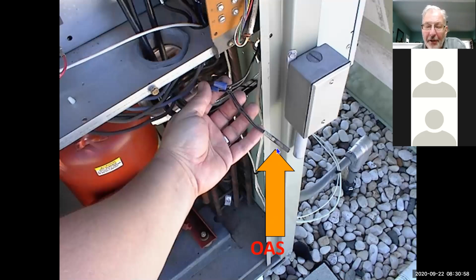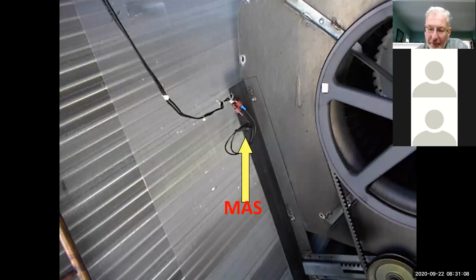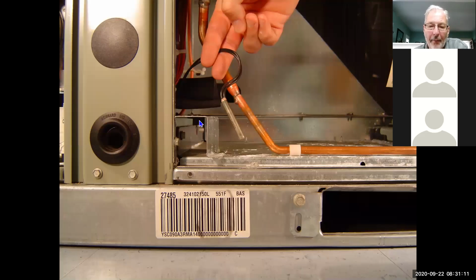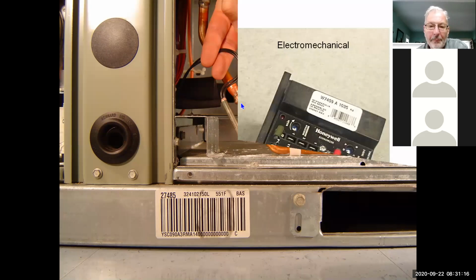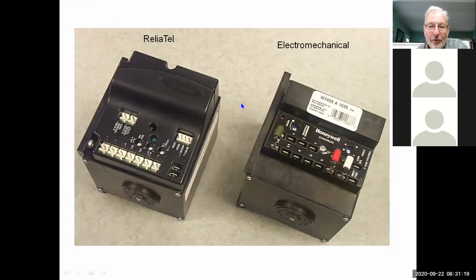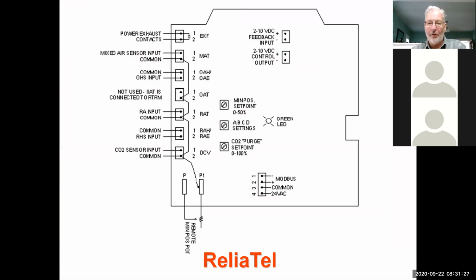The mixed air sensor on the older units is up inside this corner panel here. You have to reach back in there, grab that, and slip it out of its grommet. On the new units, the Reliatel, the mixed air sensor is down here by the foot of the compressor. And the old units, we don't use Honeywell anymore, but there was a Reliatel and there's an electromechanical unit. That's all changing as we go, in the transition of what's going on in the future here.